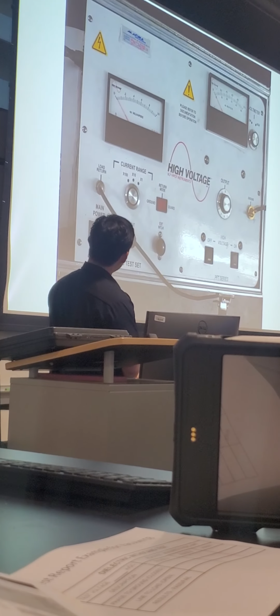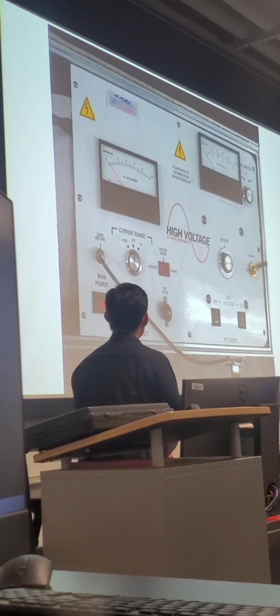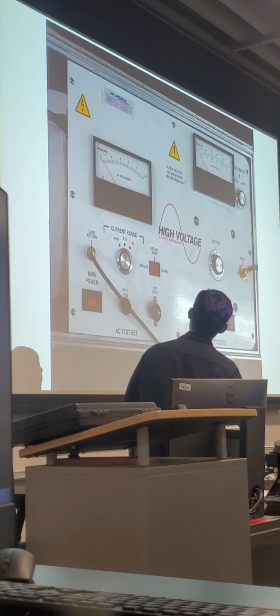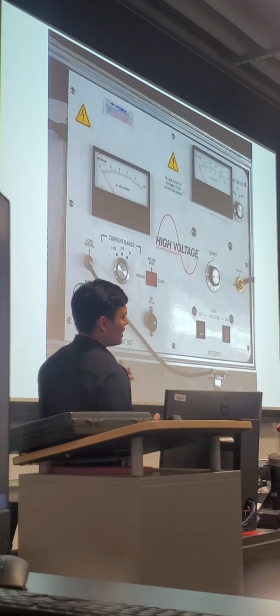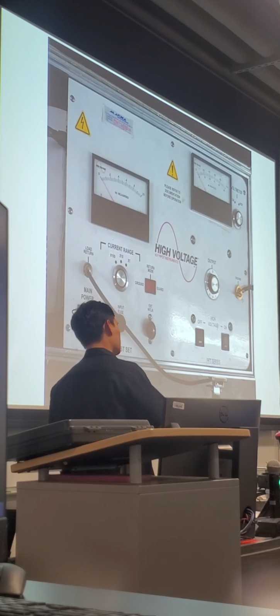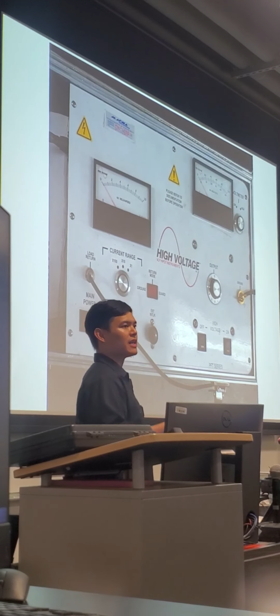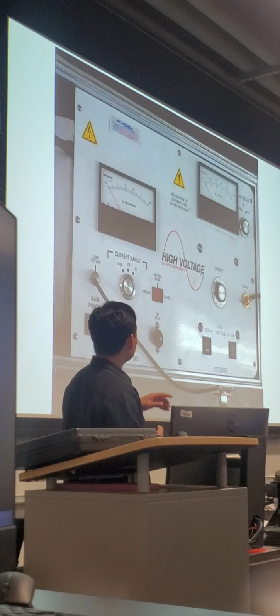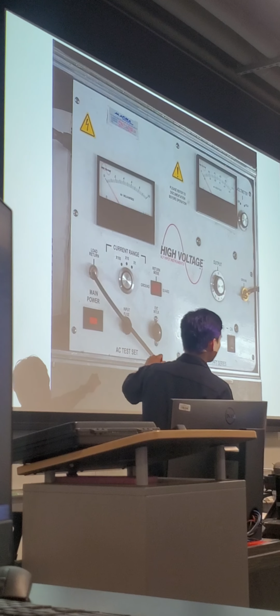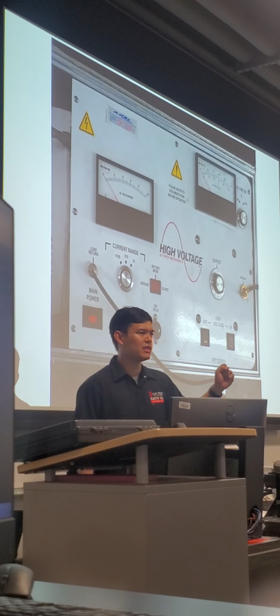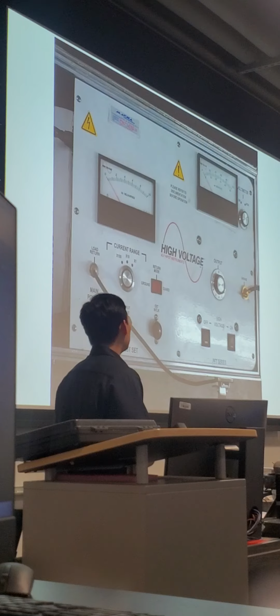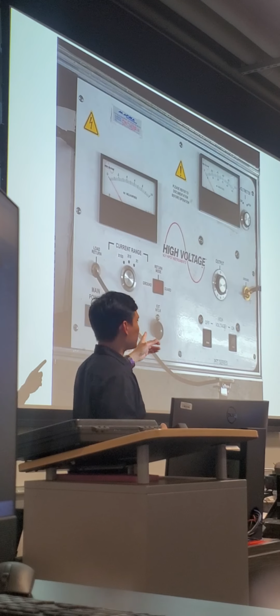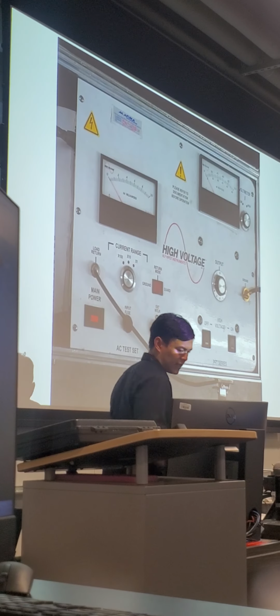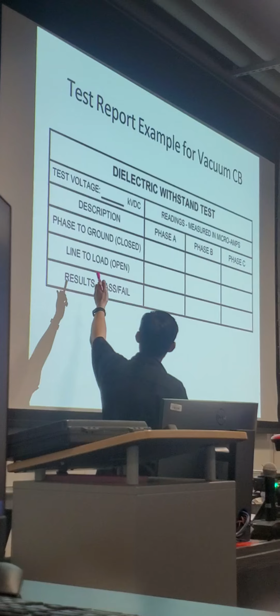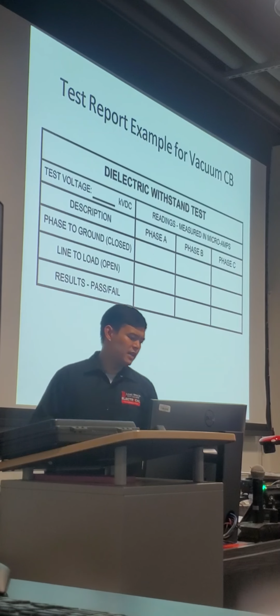So the return mode, the ground, we don't need to get too much into that, but it's dictated by your test configuration. There's the guard terminal, and there are charts that tell you how to set up your test depending on what you're testing. For example, the guard terminal on the Megger will subtract out the value it reads. This has a similar capability, but it depends on your test configuration. We're going to keep things simple and keep it on ground return mode, since we're looking at phase to ground, so the ground return will be our sensing path for the leakage current measurement.